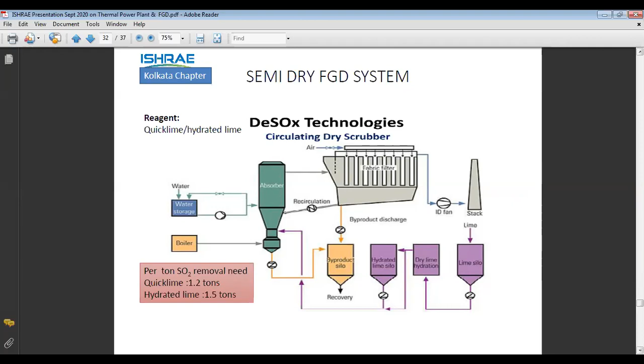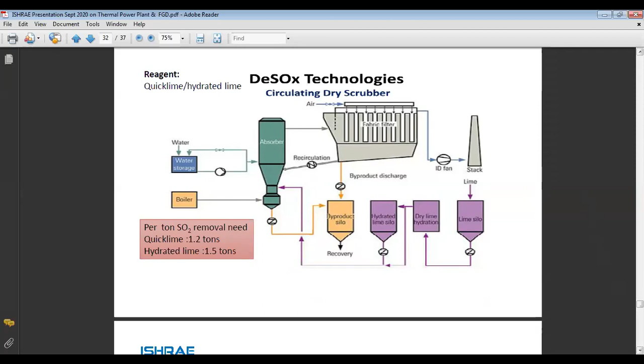But in case of this semi-dry FGD, the pH range is above 7, and it operates in alkaline media. That is why there is no need for lining of the downstream system, and also the existing chimney can be used as it is. But in case of wet FGD, you have to line the existing chimney, or a new chimney has to be installed. This is the difference. This is the semi-dry FGD.